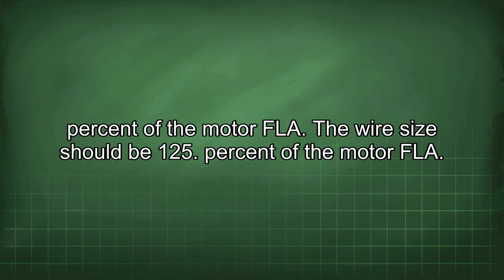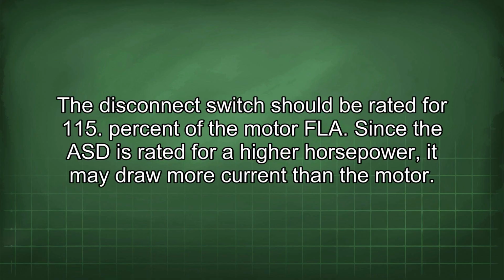The wire size should be 125% of the motor FLA. The disconnect switch should be rated for 115% of the motor FLA. Since the ASD is rated for a higher horsepower, it may draw more current than the motor.